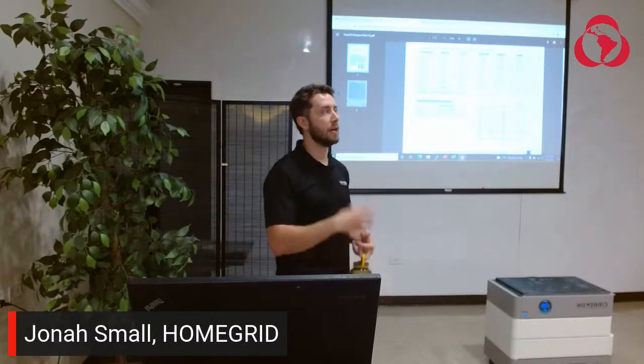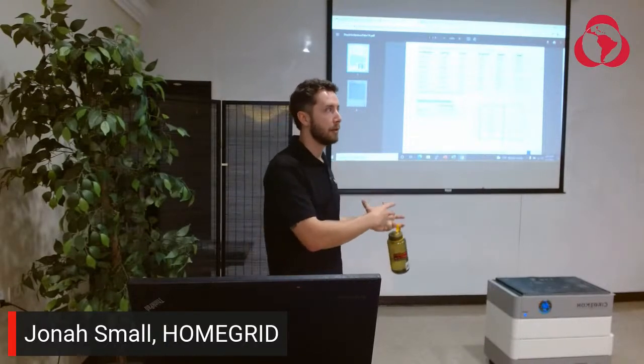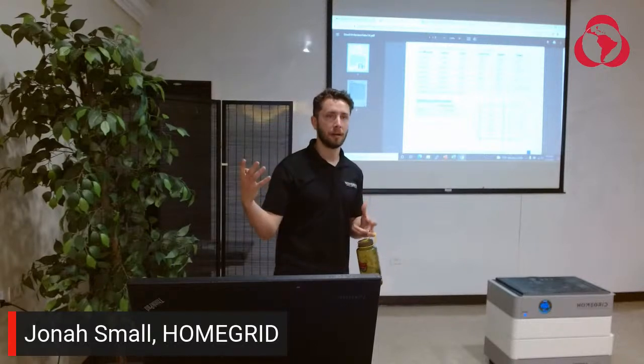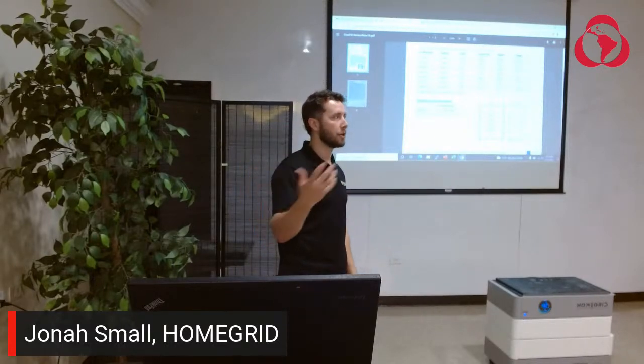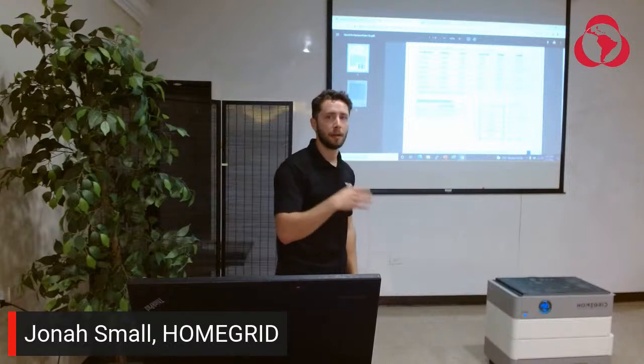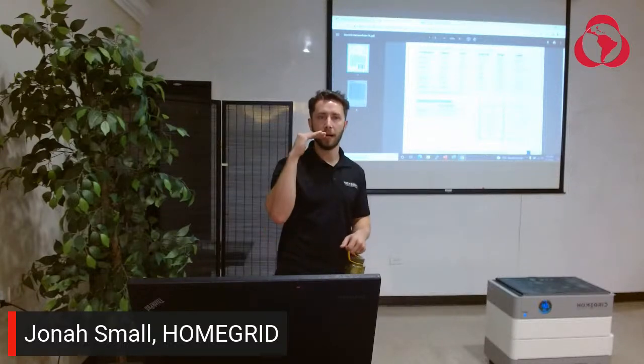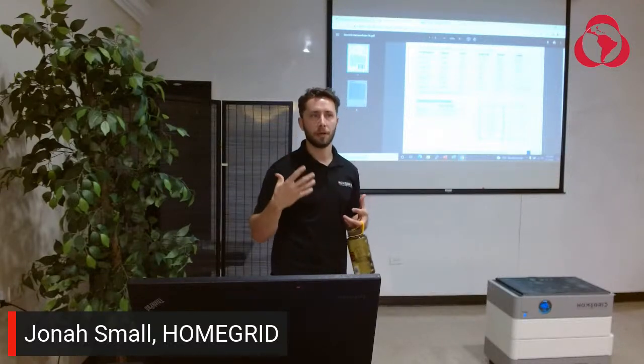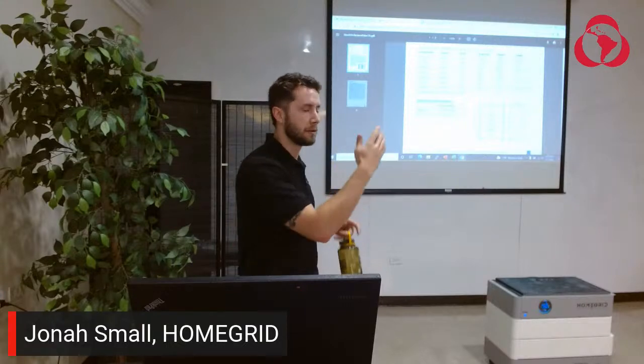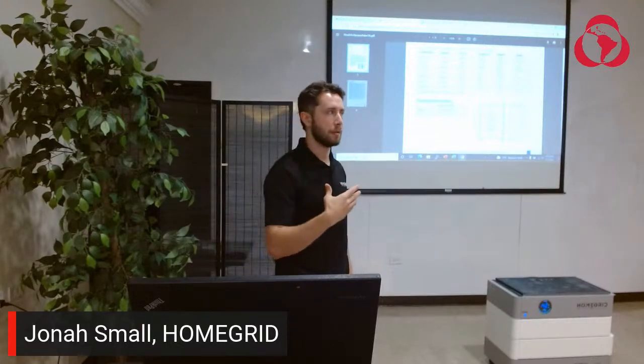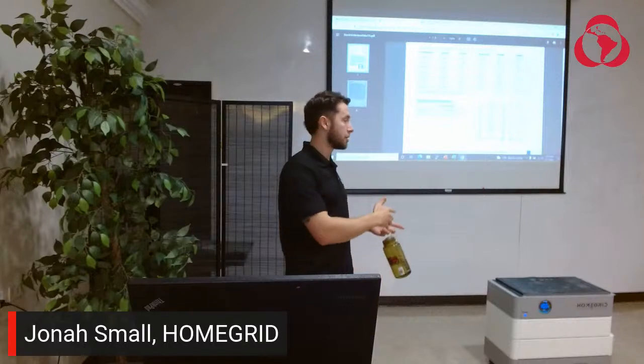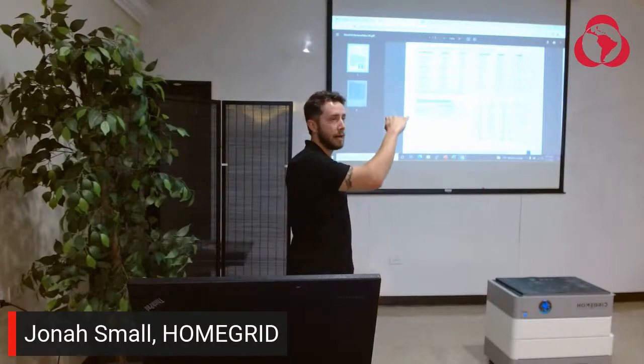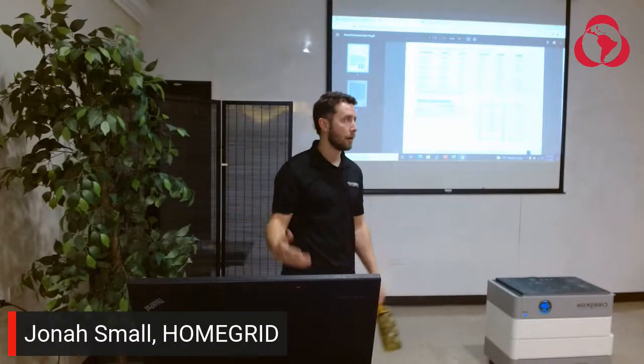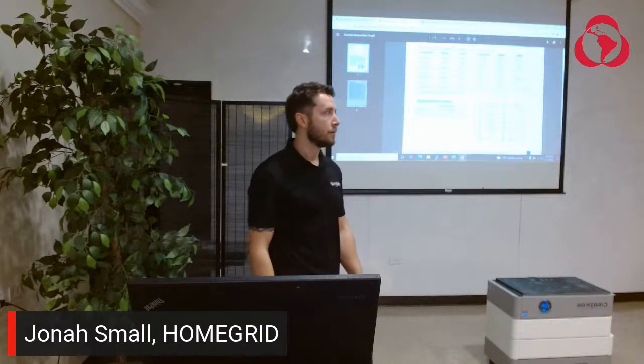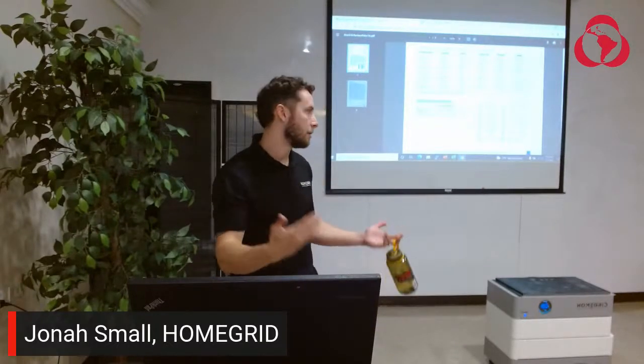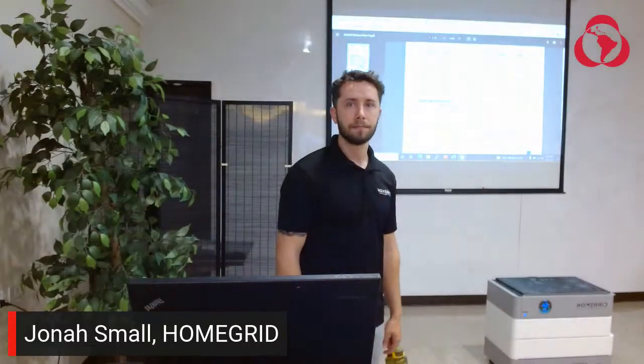The thing is, we've designed it so our battery isn't the bottleneck, but that means the solar becomes the bottleneck instead. If the solar can only charge at 185 amps, we can't utilize the full battery capacity - but that's what we always want. You could pair us with 2 inverters, 2 12Ks, and handle those loads. But if you could charge a full 8 stack, almost 40 kilowatt hours, at full capacity, we could do that in 2.5 hours, charging at 15 kilowatts.